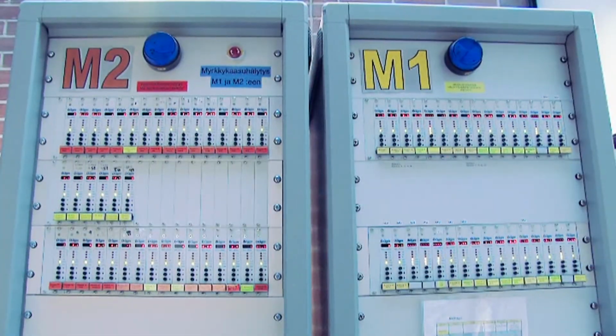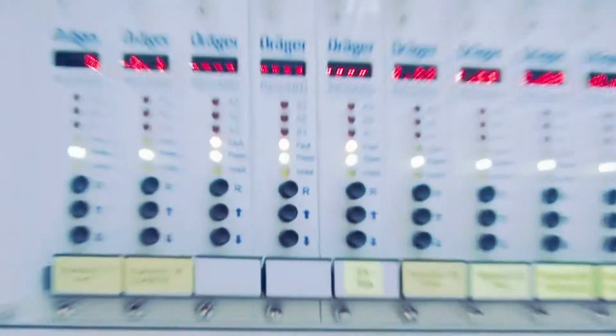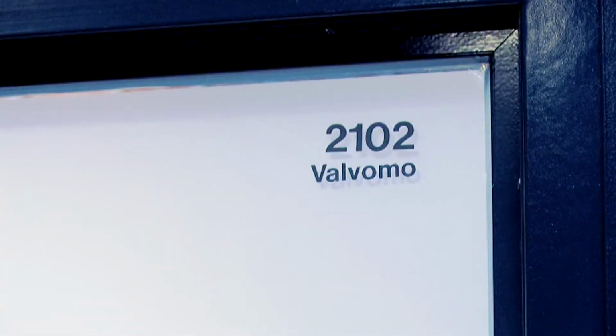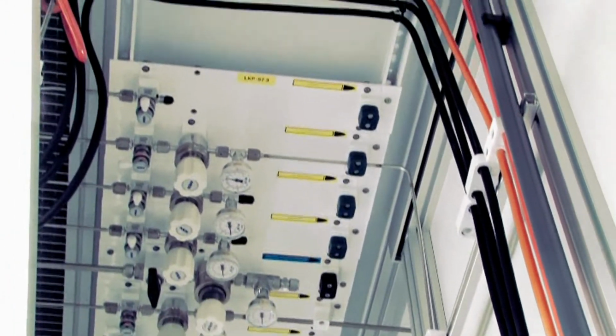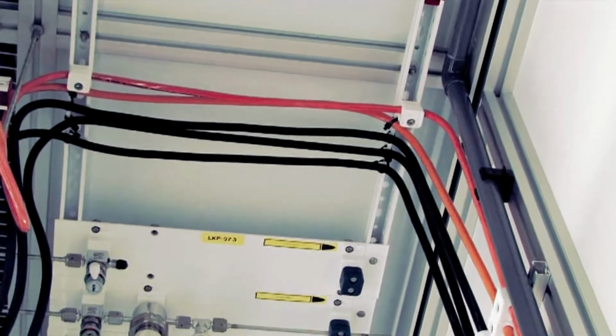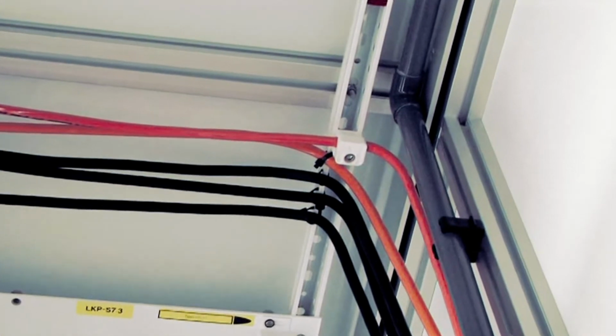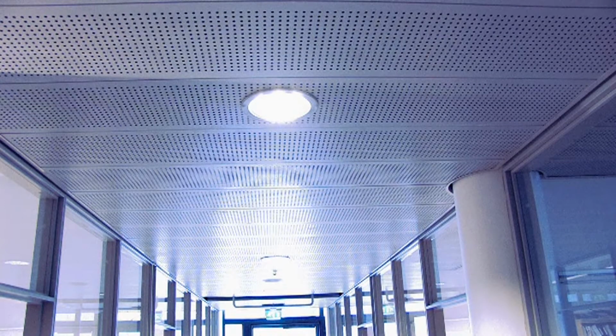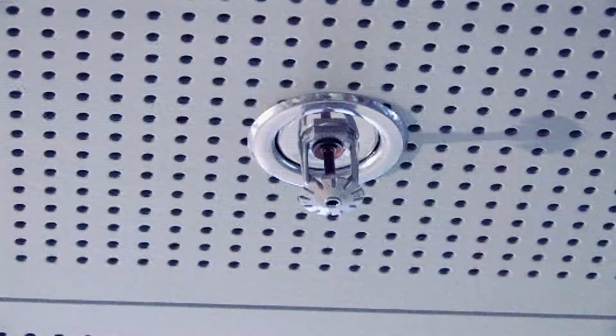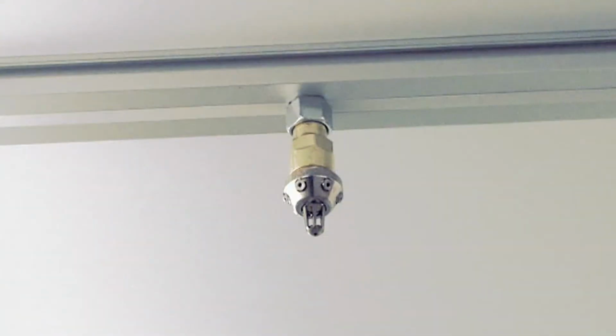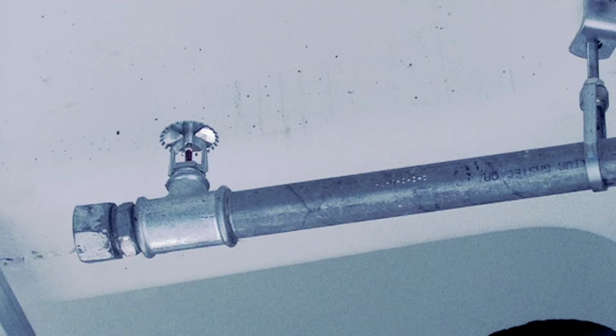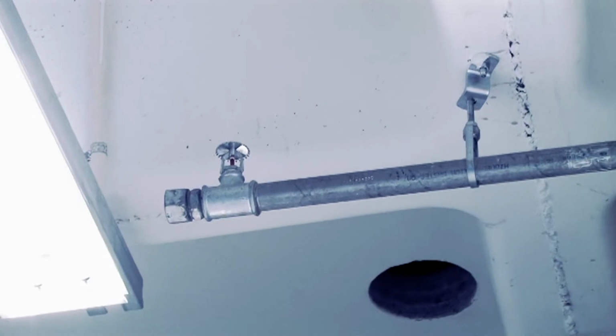Micronova has extensive fire and toxic gas detector systems installations connected to an automatic alarm system. The control units of these systems are in the control room, which is located next to the entrance to the M2 cleanroom. There are 3 different fire detection systems in the building. In the cleanroom, there is a sampling system which reacts to an increase in particle concentration. The M1 office part has a conventional smoke detection system, and the M2 office part a sprinkler system which reacts to heat. These detection systems are connected to automatic fire extinguishing systems, a water mist system in the cleanroom, and a sprinkler system in the M2 office section and technical area below the cleanroom.